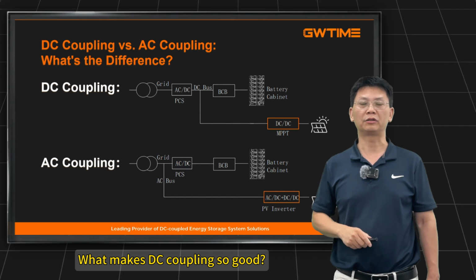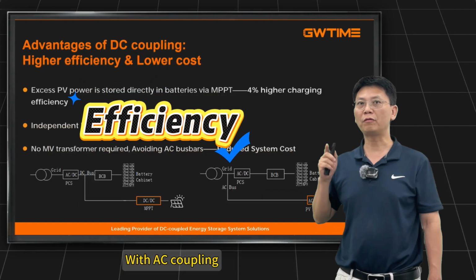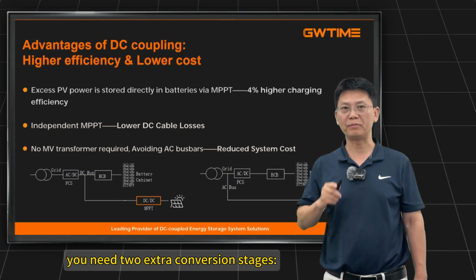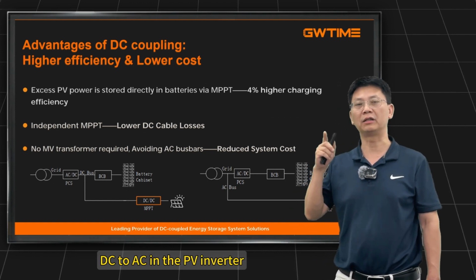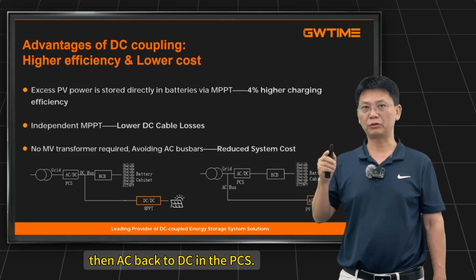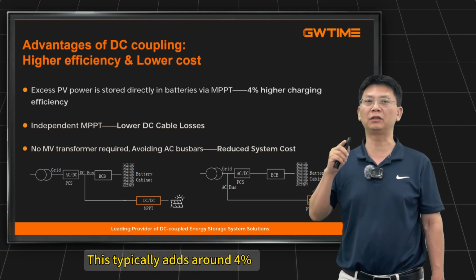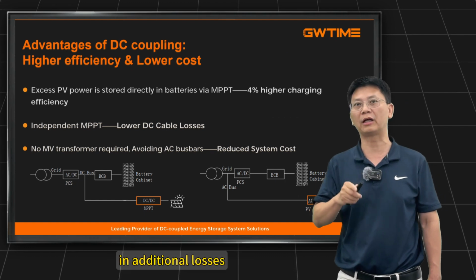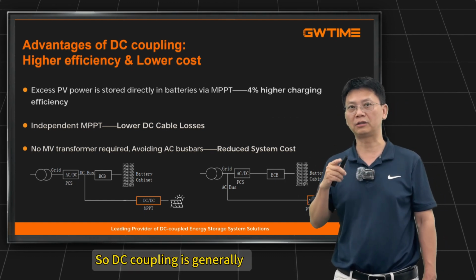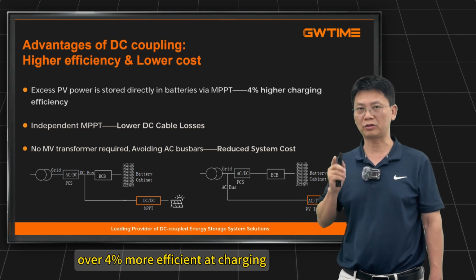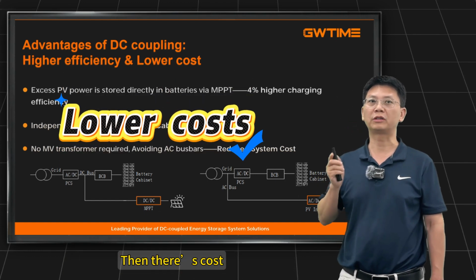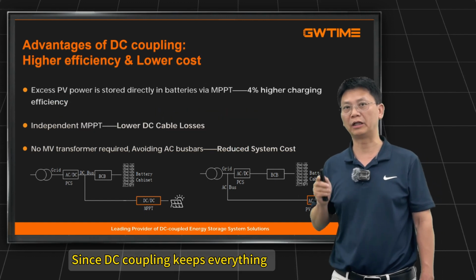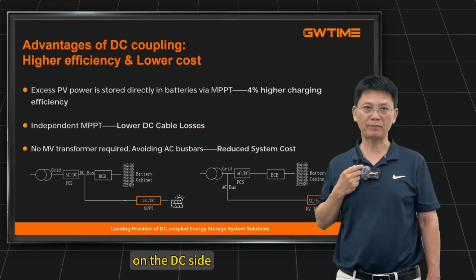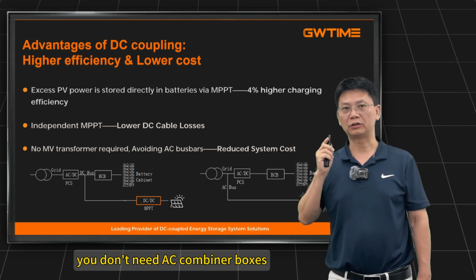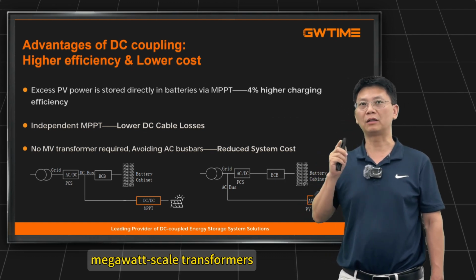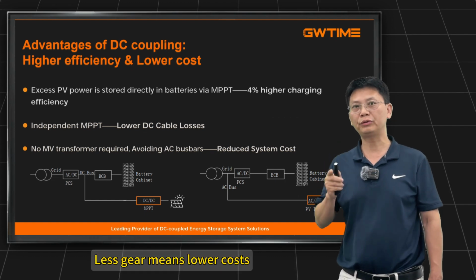What makes DC coupling so good? First, efficiency. With AC coupling, you need 2 extra conversion stages, DC to AC in the PV inverter, then AC back to DC in the PCS. This typically adds around 4% in additional losses. So DC coupling is generally over 4% more efficient at charging. Then there's cost. Since DC coupling keeps everything on the DC side, you don't need AC combiner boxes or even those expensive megawatt scale transformers. Less gear means lower costs.